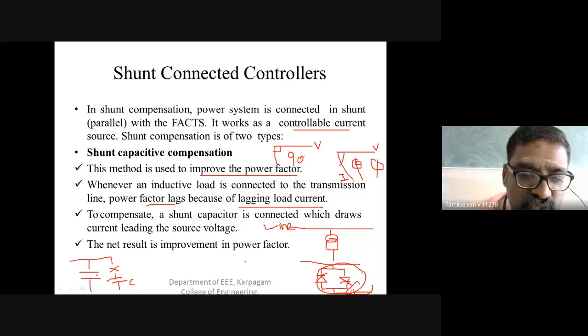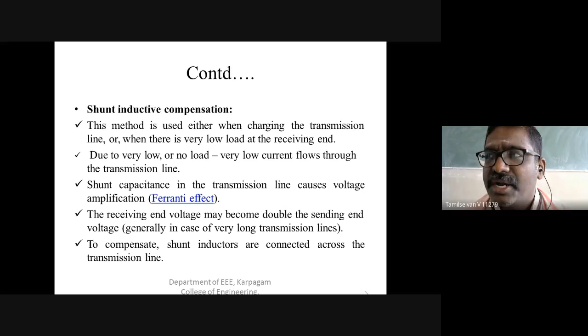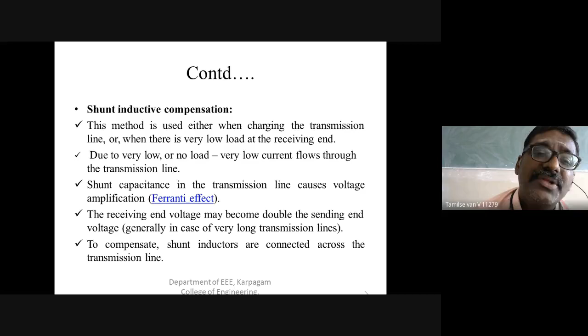That is called shunt inductive compensation. When there is low load or no load, we recall the ferranti effect discussed in Module 2: compared to the sending end voltage, the receiving end voltage will be more. So when you are under light load or no load condition, the receiving end voltage will be more compared to the sending end voltage. During that time, I want to maintain the voltage constant, and that can be achieved with the help of shunt inductive compensation.